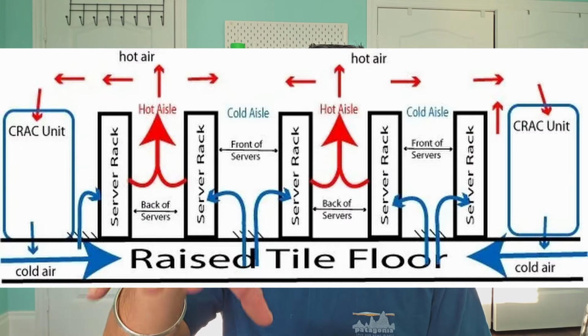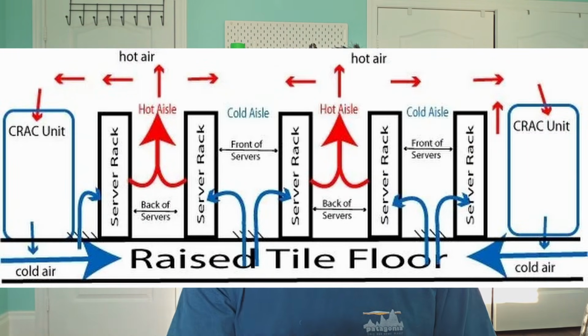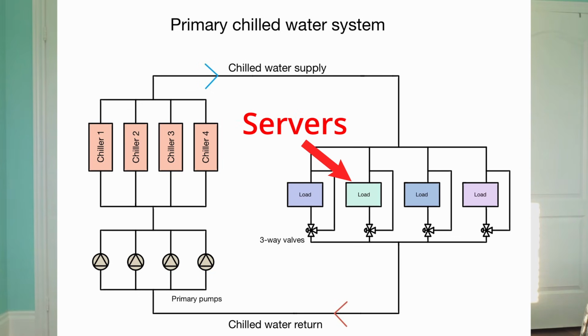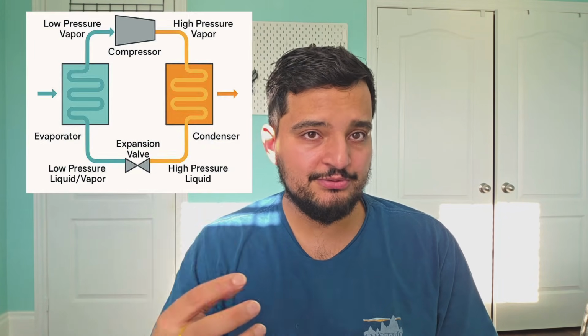water. With both of these approaches, you essentially cool down the servers and transfer that heat from the room and from the servers directly into the chilled water. So as this water circulates through the building, it collects heat from all the servers that are in the building, and that increases the temperature as it circulates. Now the question is, how do you maintain the chilled water temperature to its normal range of 6 to 10 degrees Celsius? So the answer here is simple. You use the refrigeration cycle.